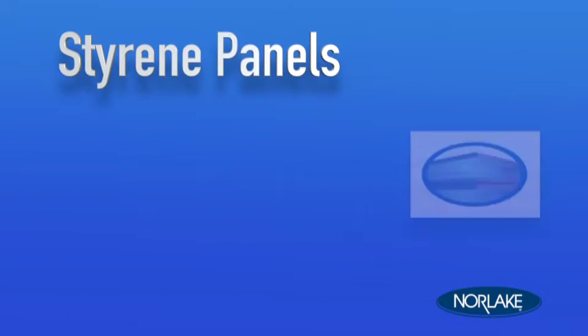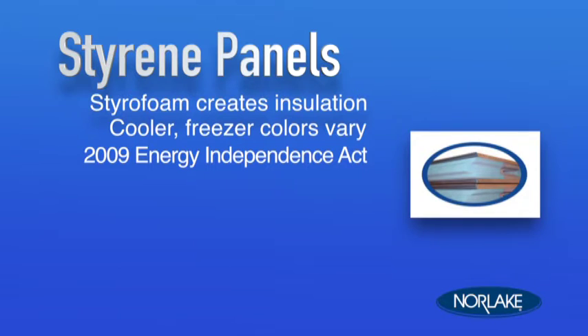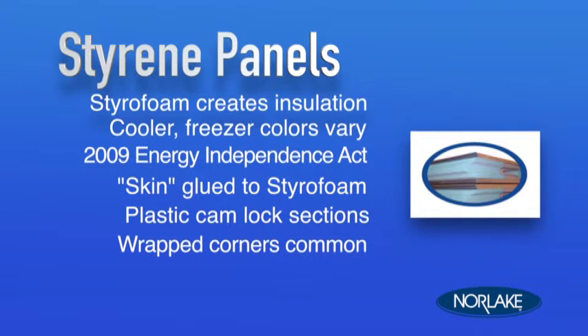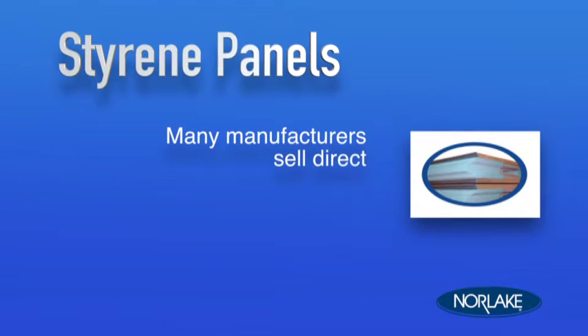Styrene panel construction. These panels use styrofoam to create the insulation. Sometimes they'll use one color foam for a cooler and a different color for the freezer. Panels will meet the 2009 Energy Independence Act. Typically, the skin is glued onto the styrofoam. Plastic cam lock sections are used. Wrapped corners are common. You usually can't mount the switch in the panel. Surface mount only. Many of these manufacturers sell direct. They're not dealer friendly.